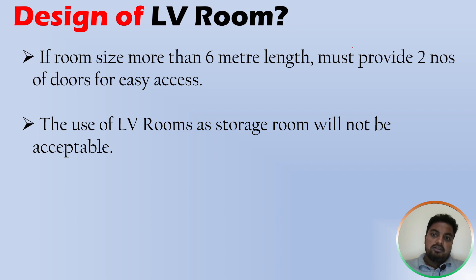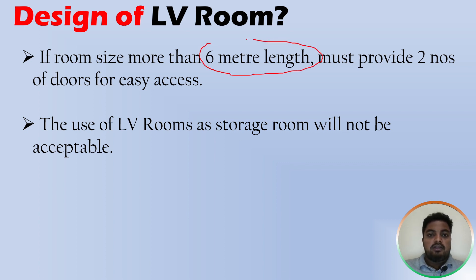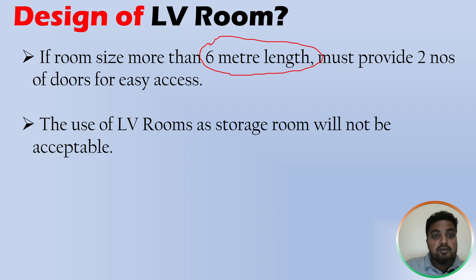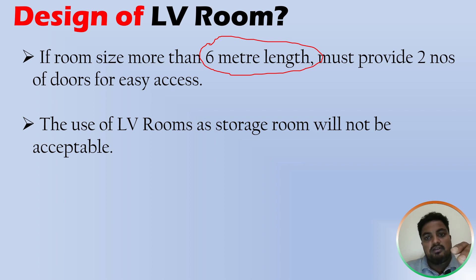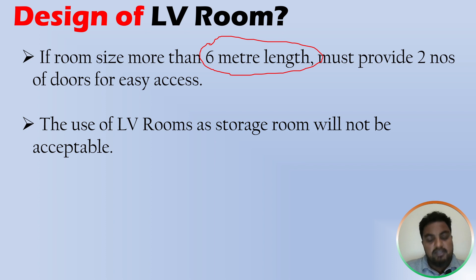If the room size is more than six meters in length, you must provide two doors for easy access. I will explain why the six-meter figure is used in the next slide. The key point to understand here is: if the LV room length exceeds six meters, two entry doors are mandatory.